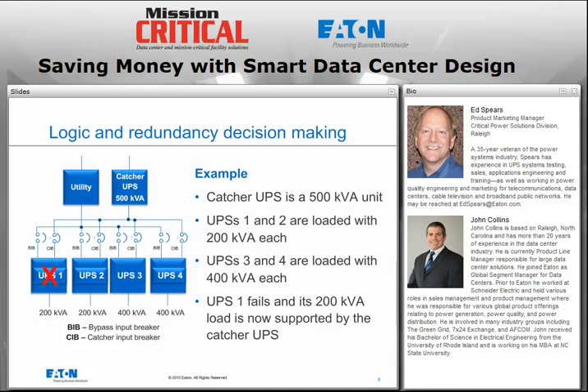And notice also that the UPSs have different amounts of load on them. They might be different size UPSs, but we're basically interested in how much load each primary UPS is supporting at any point in time. So UPS 1 is supporting 200 kVA, same thing with UPS 2. UPSs 3 and 4 are each supporting 400 kVA, and remember the catcher is rated for a total of 500 kVA. We don't want to make it bigger than we have to.